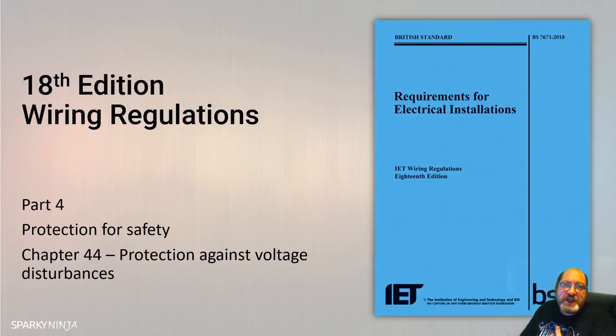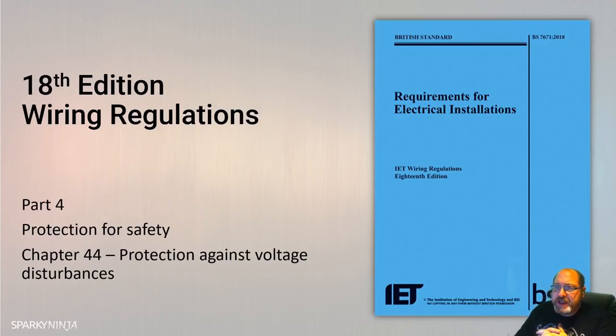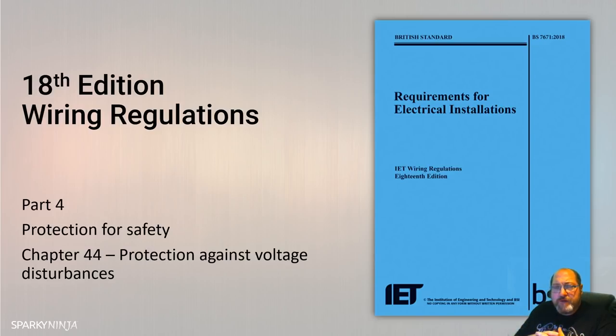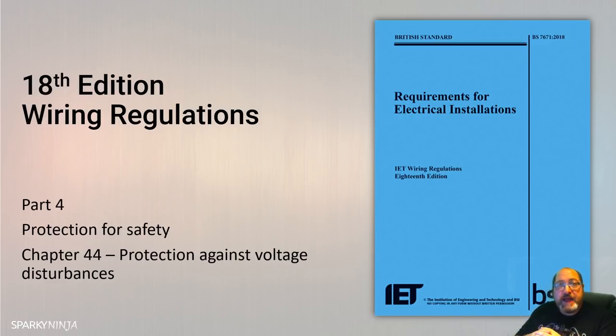Chapter 44: The Protection Against Voltage Disturbances. We're going to talk about voltage disturbances from two common causes. The first cause includes man-made events such as switching-induced loads that can create overvoltages, but also faults on the grid system such as earth faults on the primary side of the high voltage system, returning force coming back into the low voltage system. The other type of overvoltage will be overvoltages of atmospheric origin such as lightning, and towards the end we'll also talk about electromagnetic disturbances.